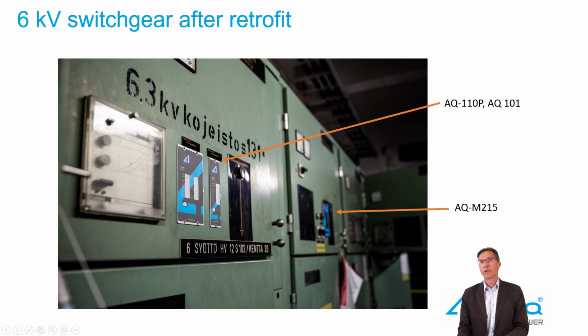Here, quite a good close-up on our AQ101 and 110 units, and you see the LED panel for exact fault location information. This is quite critical, since if we would have an arc flash incident in this particular switchgear, where we have the arc quenching device sitting, there is really very limited burn marks or any other information of the fault location in the switchgear, since the operation time is limited to less than 6 milliseconds. So these LED panels are very important. They will pinpoint you to the actual fault location based on which sensor found the fault.